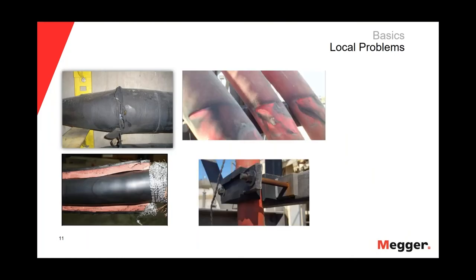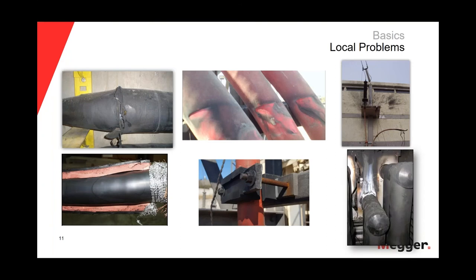In terms of local problems, some pictures in this slide show some of the classic problems related to workmanship issues or manufacturing defects. Starting from the upper left corner, we have a transmission splice that blew up because it was assembled incorrectly. Below, we have a medium voltage heat-shrink splice where the material was not heated uniformly, the shrink material was not completely contracted, and that void created problems with partial discharge.